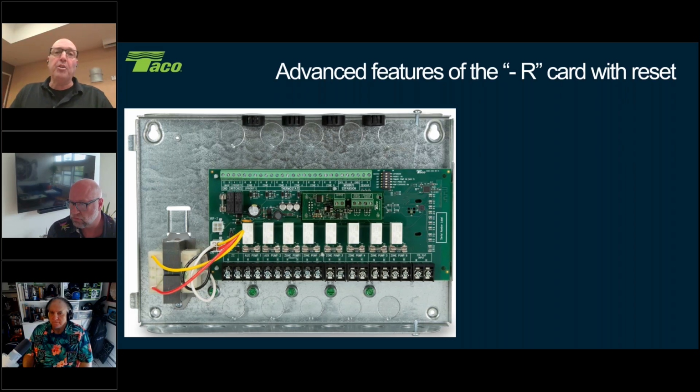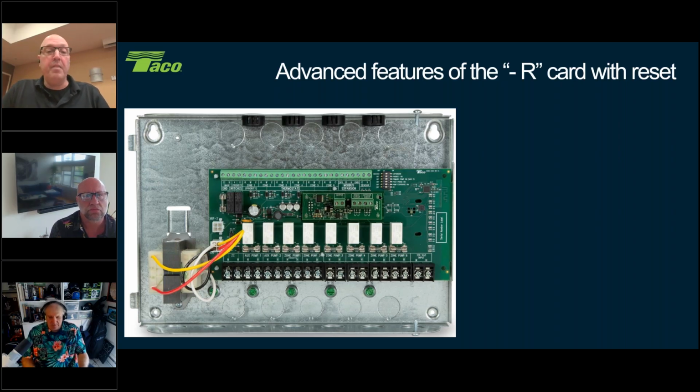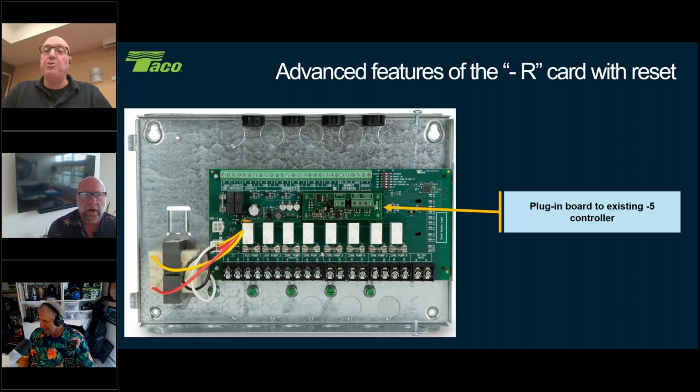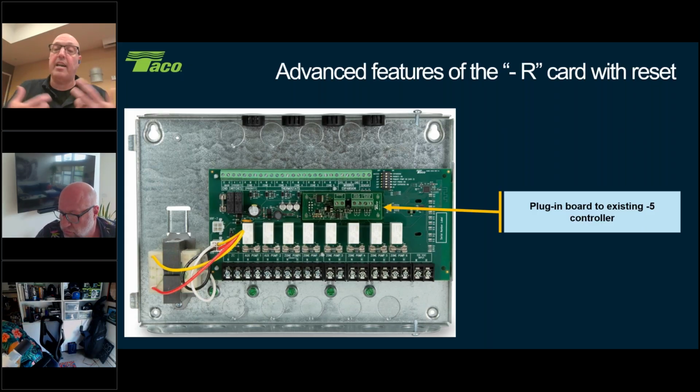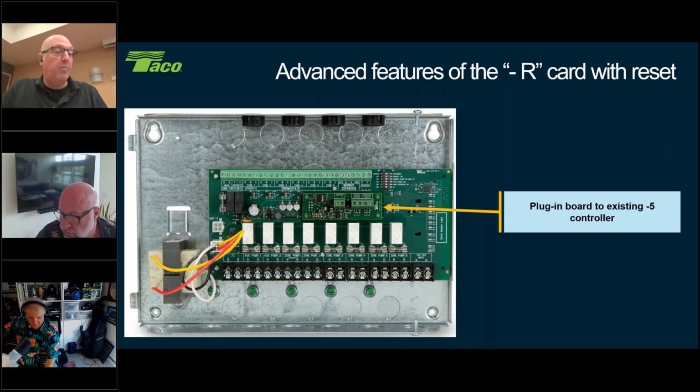And the reason why we left it as a separate item is because some of these features might be built into the boiler, maybe not, or you might find the features are needed for an older system or even for a newer system, but these controls were already installed. It could be added to any Dash 5 control except for the 501. The SR 501 you can't add it to, but anything else on the SRs or ZVCs, you can add the PC 800 to. It comes with 4 posts and there's a terminal that you can easily lock it right down. It's not hard to do. Even I can do it. And I didn't short anything out on the board either.